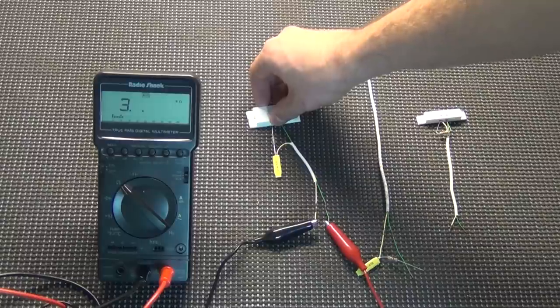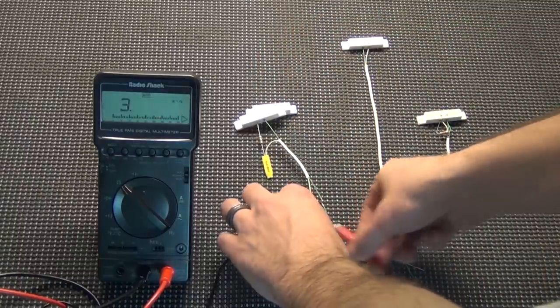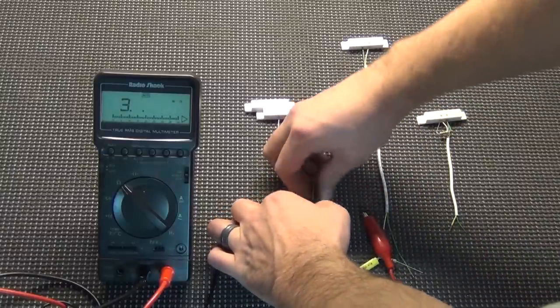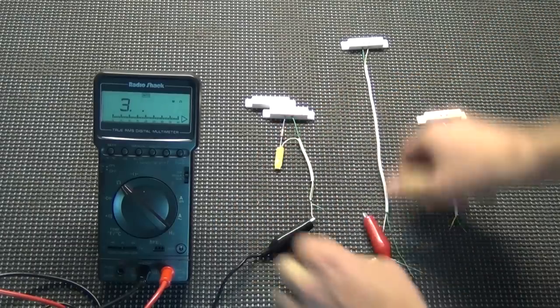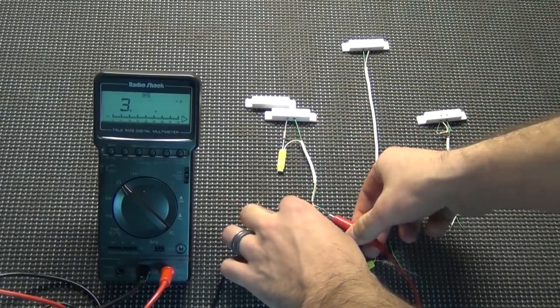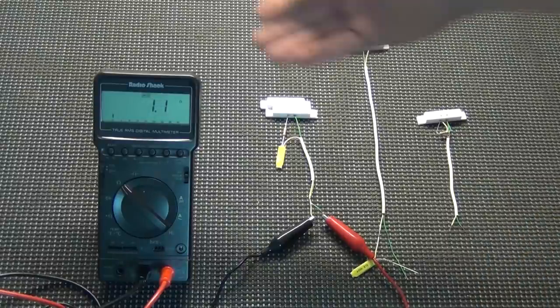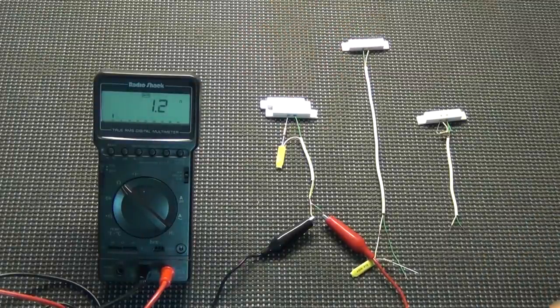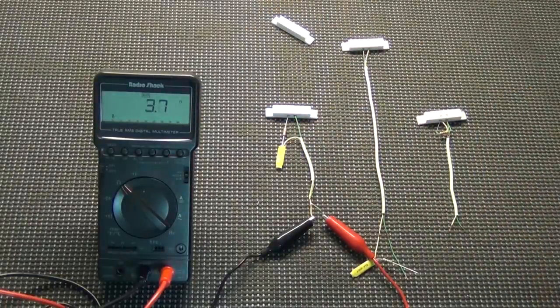When it's closed again, it goes back to 5.6K. Now I'm going to twist these wires together to create a short. Now you can see basically no resistance — showing 1.2, 1.3. That's with it closed. If I open it up, it's still showing basically no resistance — the panel can't detect that short.